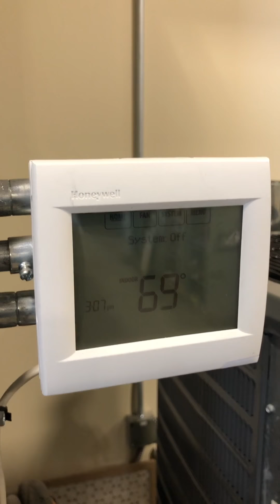And then it also has low voltage. It's going to get a signal from the thermostat to tell those switches to close or open with the low voltage signal. And when they close, they'll pass high voltage to the strips, or when they open, they'll cut high voltage to the strips and the strips will turn off. Stack sequencer. Same concept as the contactor. It uses the low voltage signal from the thermostat to open or close based on what the thermostat is telling it to do.